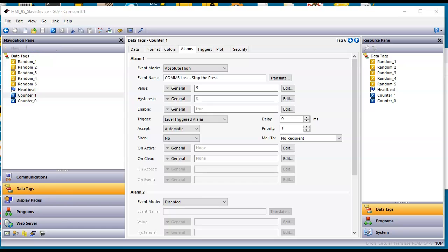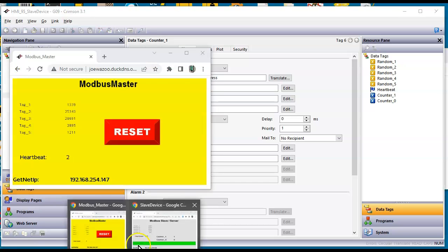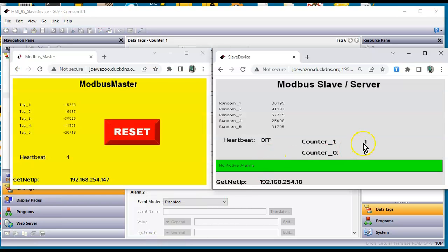So if I go back to our demo here, there's the Modbus slave. You can see it's all working great and everything's going good. Heartbeat here, what have you. If I hit the reset button, this guy cycles power, the stop counts. But look, this guy starts counting. So wait a minute, too many numbers have gone by with no change. It now causes an error. So that's a simple way that you can monitor something as a Modbus slave device.